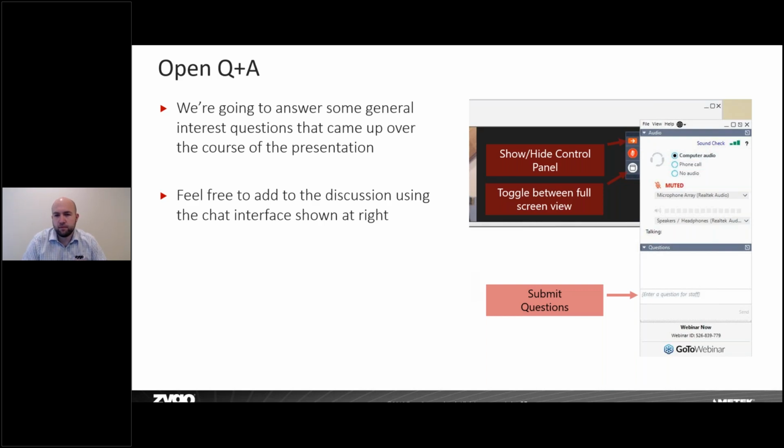Next question here. What is the steepest angle that you can characterize? So the steepest angle is going to be dependent on which objective you used. As you go to higher magnification objectives, you're generally going to go to a higher numerical aperture, which is going to allow you to measure steeper surfaces. If we go up to something like a 100x objective, we've been able to measure surfaces as steep as about 70 to 75 degrees.